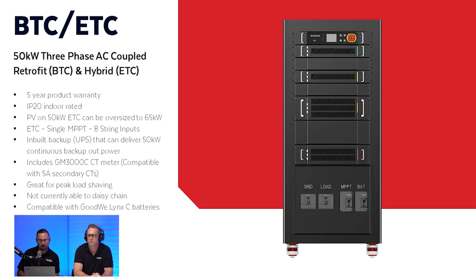Now, it comes with a GM3000C energy meter, which allows you to pair it with 5 amp secondary CTs, so it's not an issue. Depending on the main switch current rating, you can just simply size the CTs to suit. Great for peak load shaving. The ETC model with the solar inputs is a single tracker. You can connect up to 8 strings. Now, if you're familiar with designing systems with Fronius inverters, a lot of those inverters, the Eco series, only have a single tracker. However, that doesn't mean you're only limited to one orientation. Very often you'll have a north, east, west parallel. So the single MPPT isn't a problem in the designs I've come across.